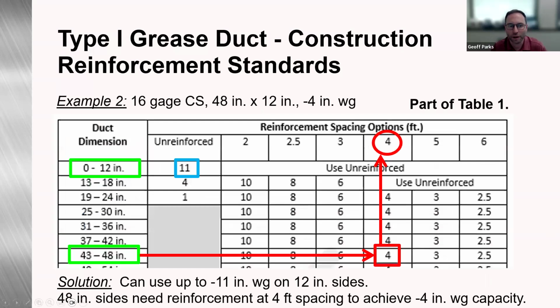Now, if we look at something a little bit bigger, here we're going to have 48 by 12, negative 4-inch water gauge. So again, we're back on table 1. This is just part of it, but we're going to look at the 48-inch size. And then we're going to come to right here, and this is saying at 4-foot reinforcement spacings, we're good up to 4-inch water gauge. So on the 12-inch side, obviously we know from the previous example, that's good up to 11-inch water gauge. We're not going to have to worry about anything. But the 48-inch side is going to need a reinforcement, and that reinforcement spacing is going to be 4 feet.